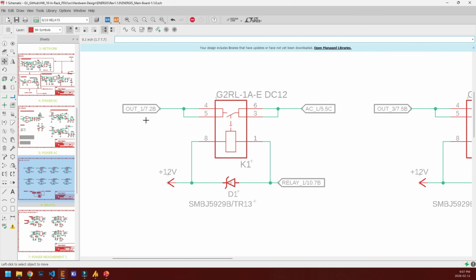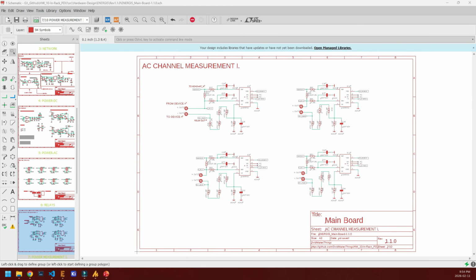D1 through D8 are flyback Schottky diodes. When the relay coil turns off, the magnetic field around the coil collapses. The energy, which was stored in the form of a magnetic field, induces electrical current, and this creates a voltage spike. Without the diode, that spike would flow back to the driver and it would destroy the driving transistor. The diode clamps the spike to about 0.4 volts above the supply. Schottky diodes have lower forward voltage than standard diodes, and they respond faster, and generally they are better protection for inductive loads. Right next to the relays, the output measurement is sitting.